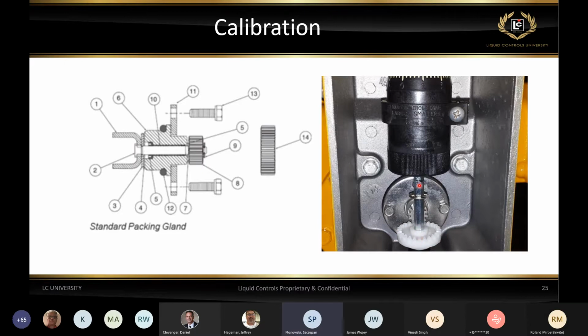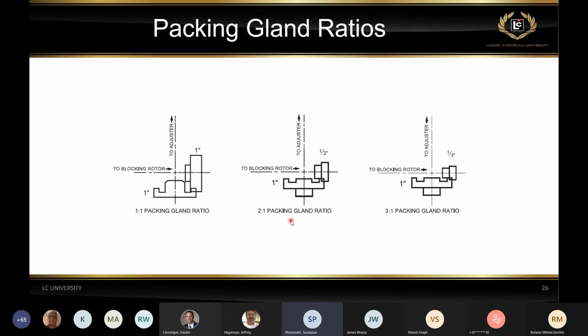Phase gear is sitting on a hex shaft that's going up, in this case to the adjuster, or possibly directly to the electronic registration. Now, one part that's extremely important as far as mechanical registration is the ratio between the phase gear, which is the white gear, and the packing gland gear. Currently, we use 3 different ratios depending on size of the meters, units of measure, etc. And you have a 1-to-1 ratio when our white phase gear is 24 teeth and the metal packing gland gear is also 24 teeth. So it's a 1-to-1 ratio.